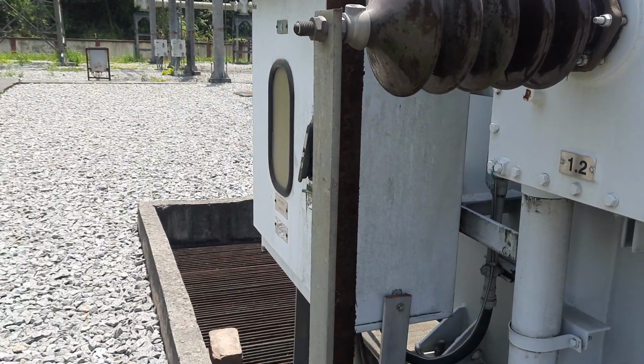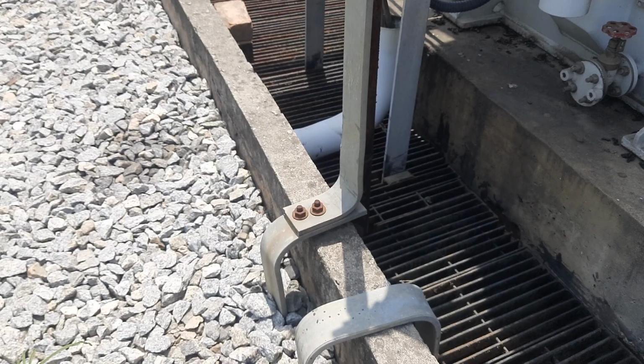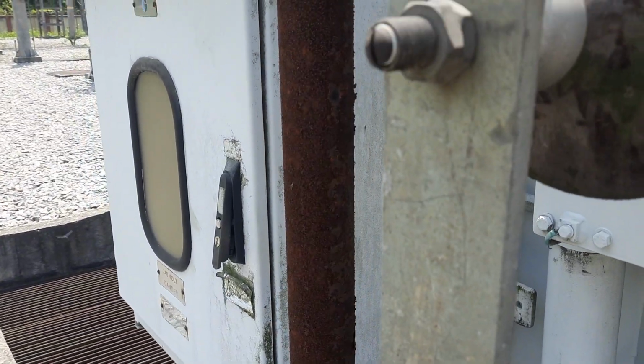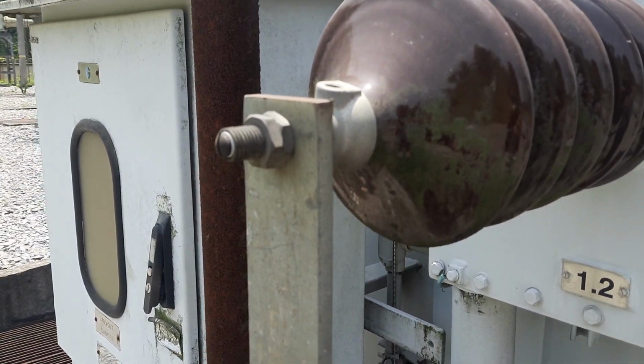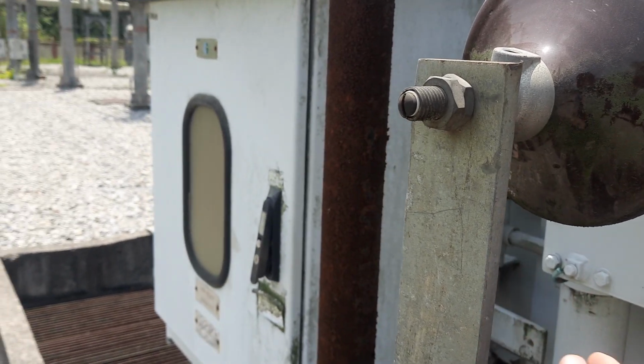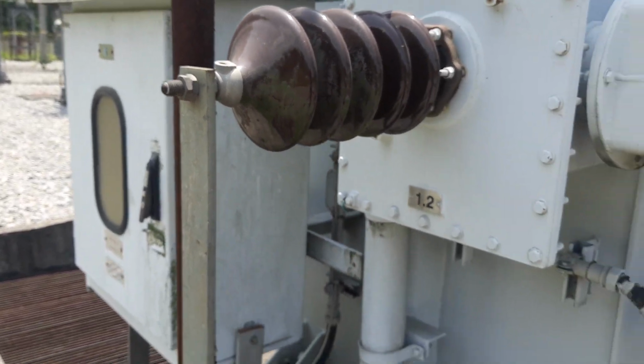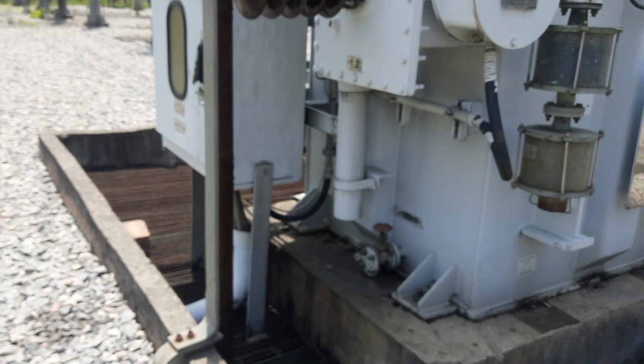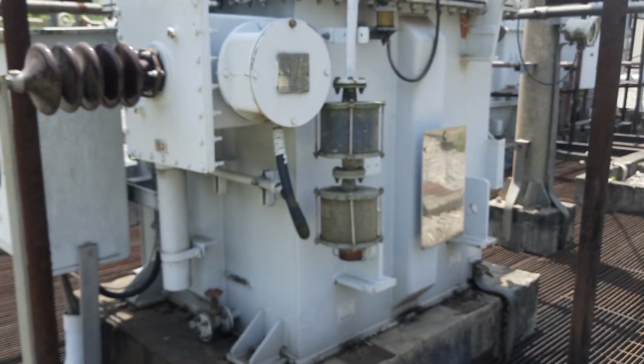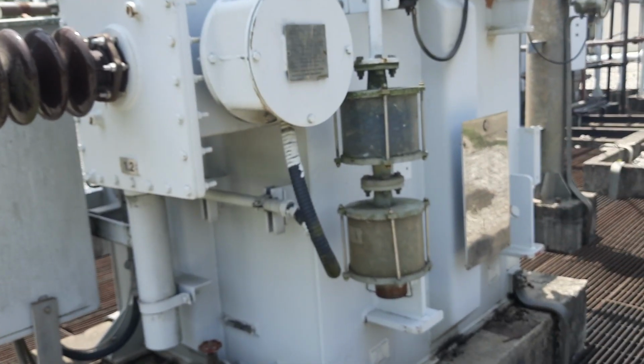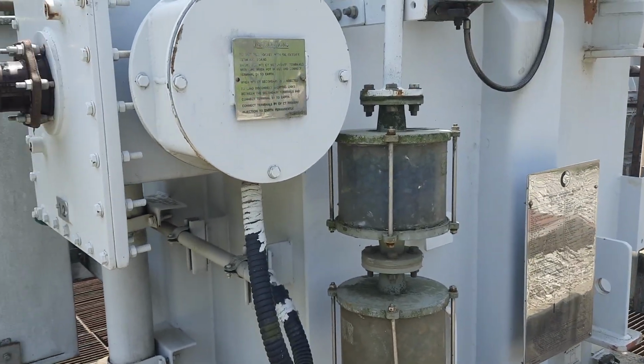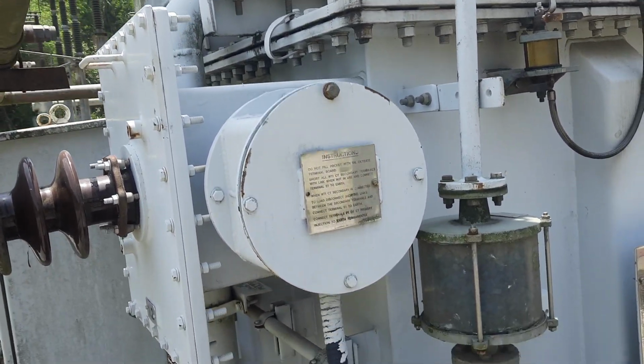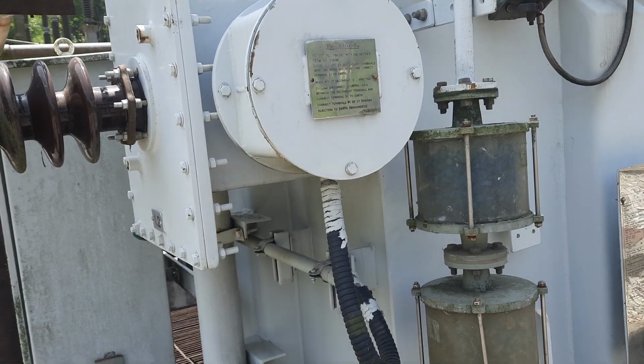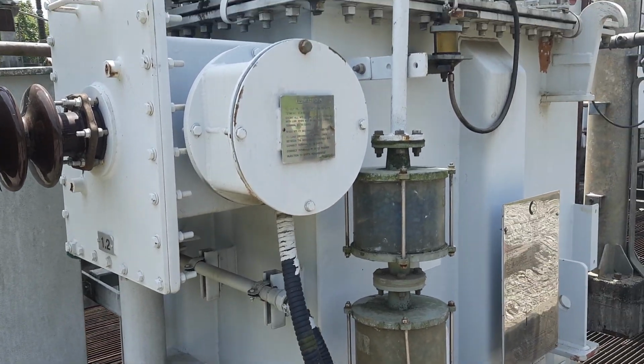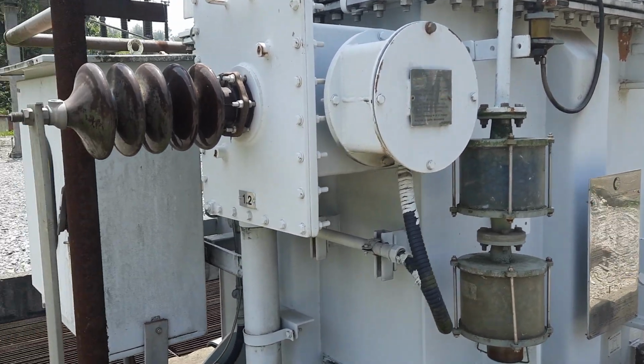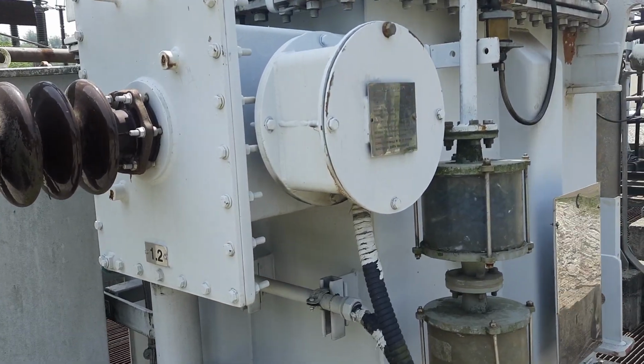terminal. It is properly grounded, because you may think that this is having current, it should have current, but the earthing is good enough to absorb everything. That's why even if you touch it, nothing happens. And this is our silica gel. You can see the CT is also there, just for the protection system. Whatever current flows through this will be recorded in this CT.